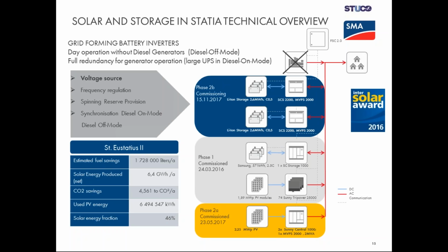After this iterative design process, we provided 2 Sunny Central Storage 2200 grid forming inverters as completely redundant. So we have 3 battery inverters in operation in parallel, and if any of those fails, 2 take over, smoothly, seamlessly. And we were very happy to win, for instance, the CAREC award last year in Miami.